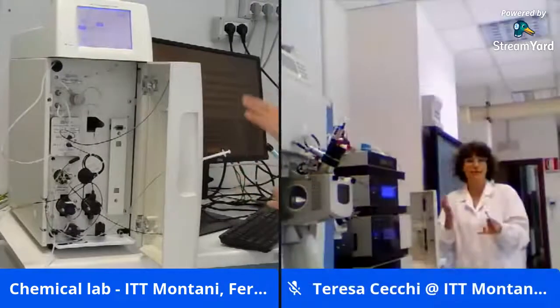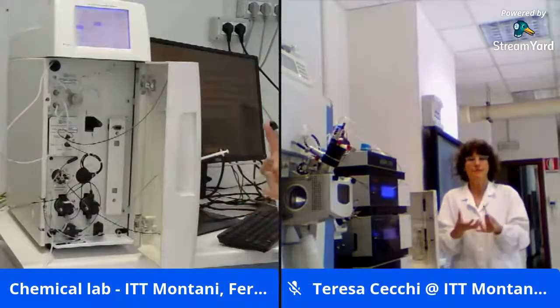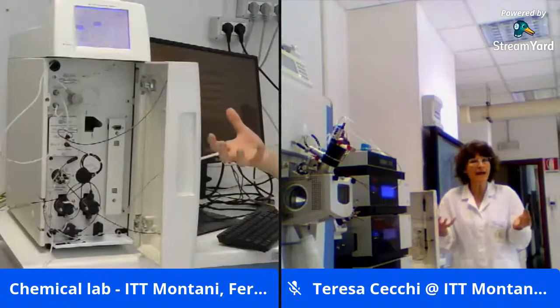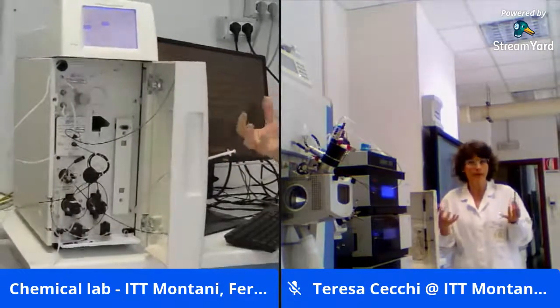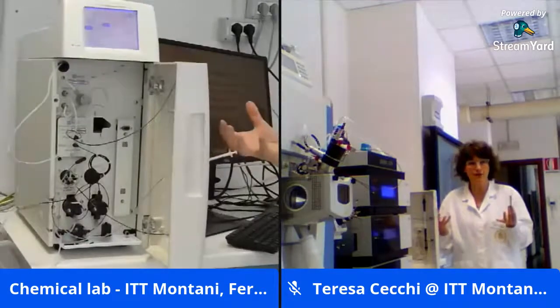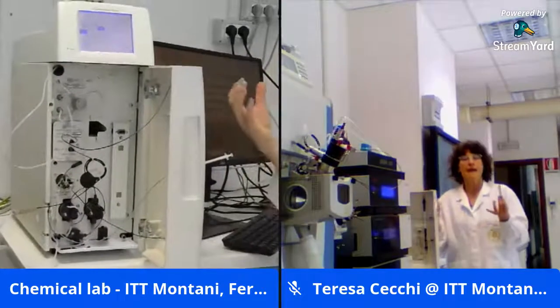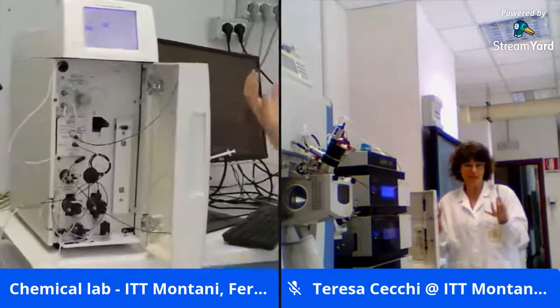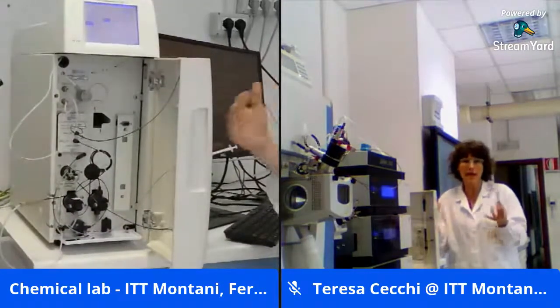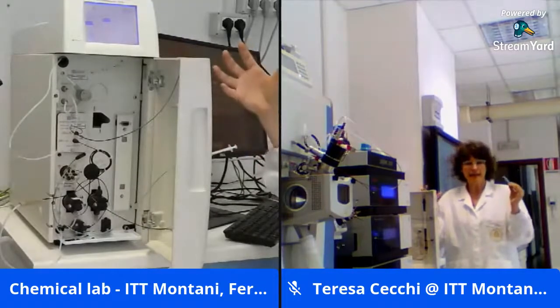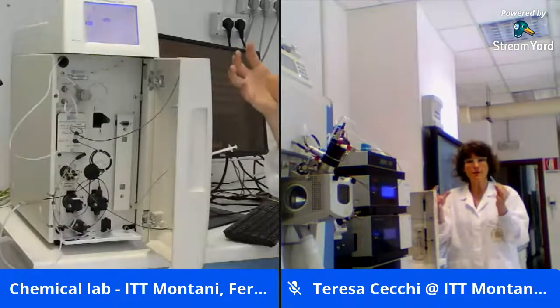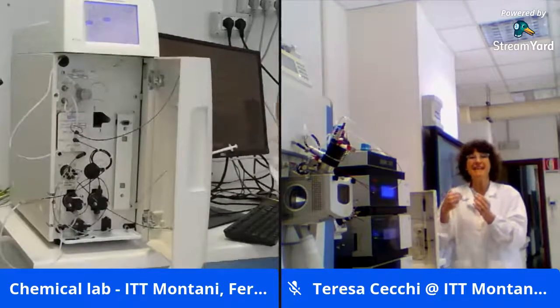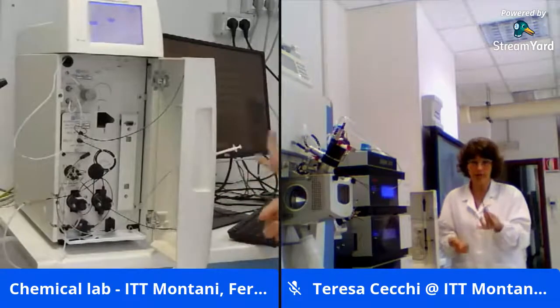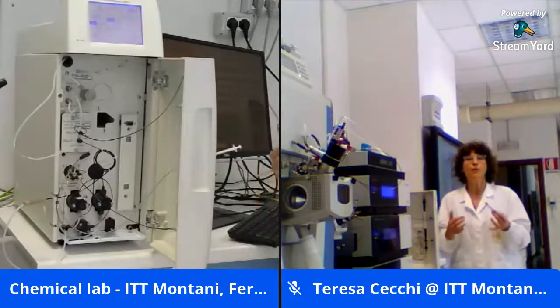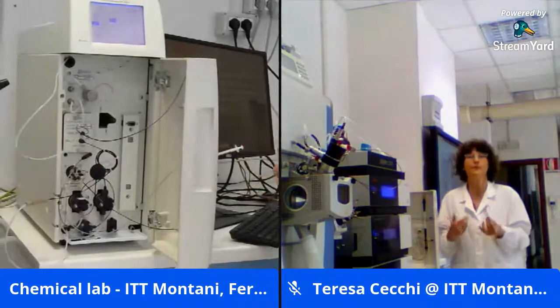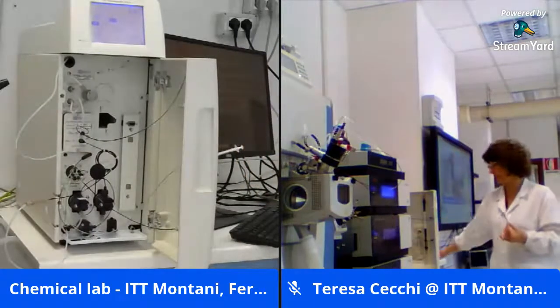When it feels the stroke, the pulsation, the spring would expand, thereby absorbing and storing the excess kinetic energy of the pulsations. And when we have no strokes, the expanded coil would return to the original position, thereby delivering an extra flow of liquid. In this way, we can almost eliminate pulsation and pump strokes.